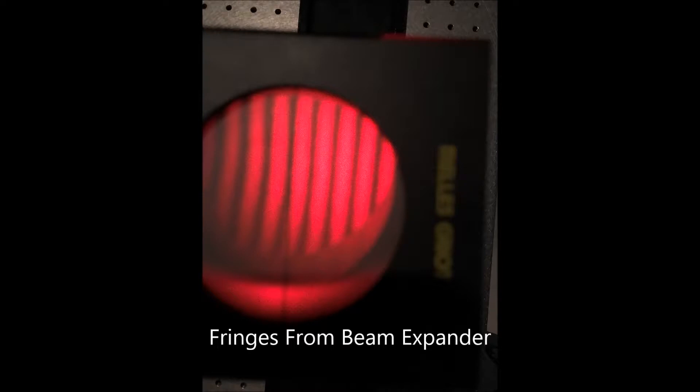We checked for collimation with the wedged shear plate and translated the collimation lens in Z until the fringes were parallel to the reference line.